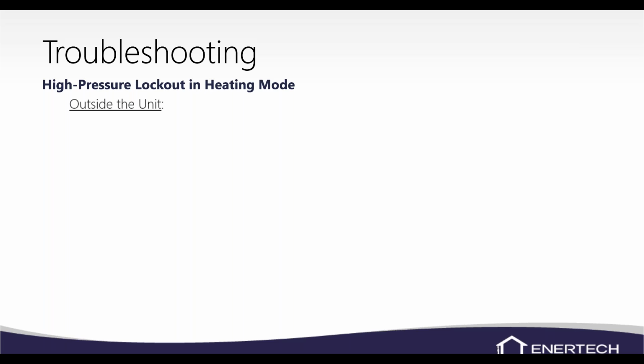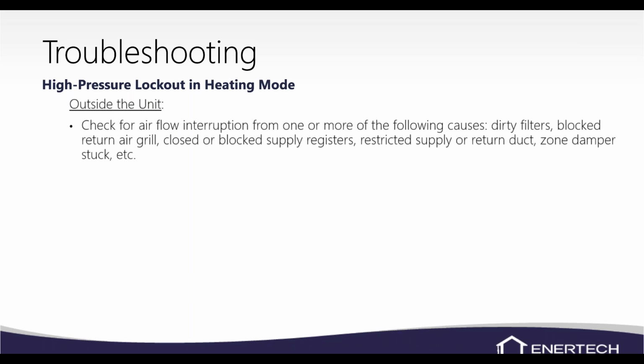We're going to be looking at our load hydronic zones. And if it's a forced air unit, we're going to look more towards your blower, your airflow, the filter plugged up, something like that. So outside the unit, we want to look for airflow interruptions. So dirty filters, blocked return grills, blocked supply registers, restricted ductwork, zone damper stuck, no bypass damper if you've got a zone system.